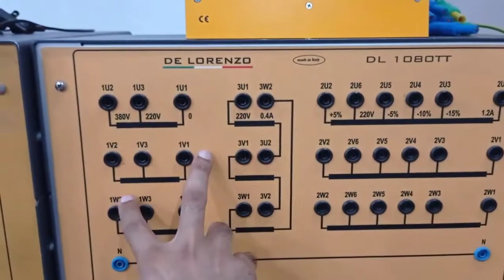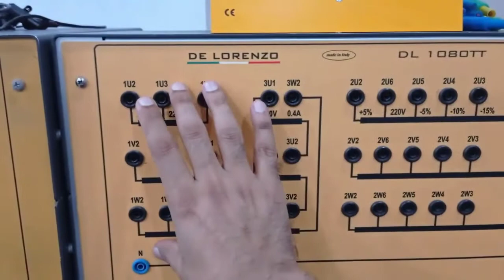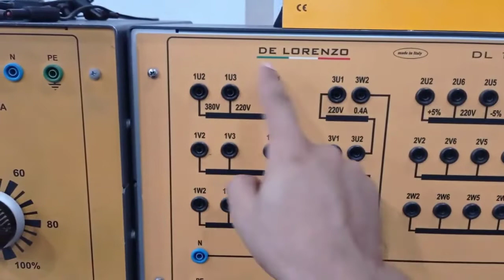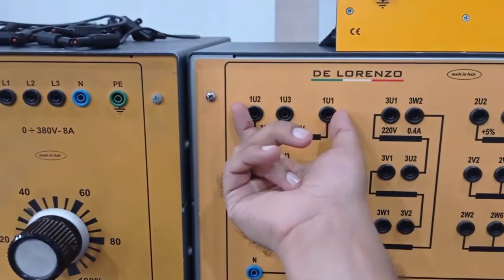This three-phase transformer has three windings. This is winding 1, winding 2 and winding 3. We will use only the first winding and the third winding. According to the instructions, you will have to connect this first winding in delta formation. Use the full 380 rating of this winding, these external two terminals. If we use the internal two terminals, the rating of the winding will become 220. Use the external extreme two points, 380 volts, and make a delta of these three windings.